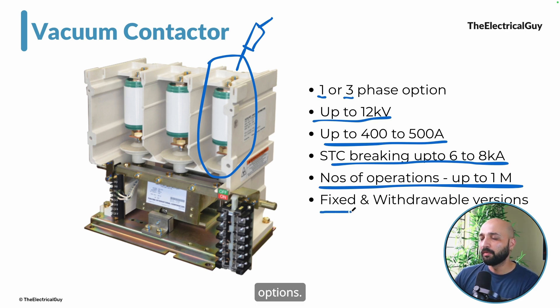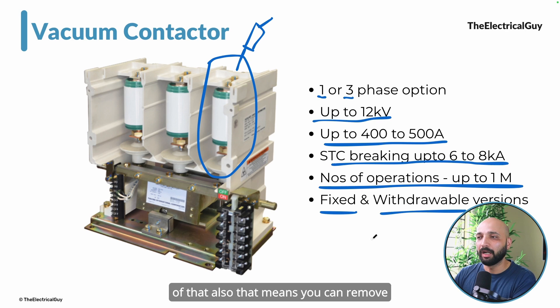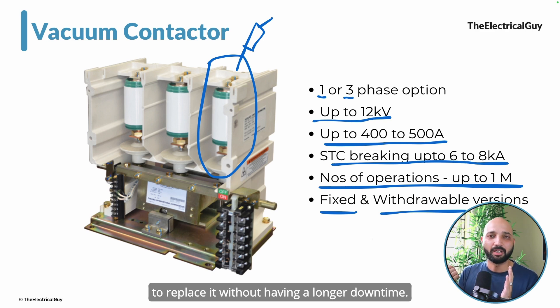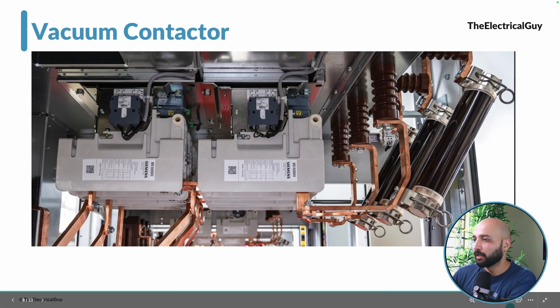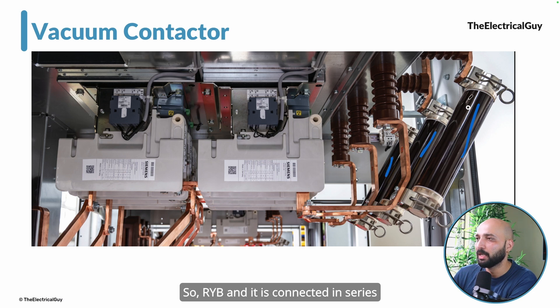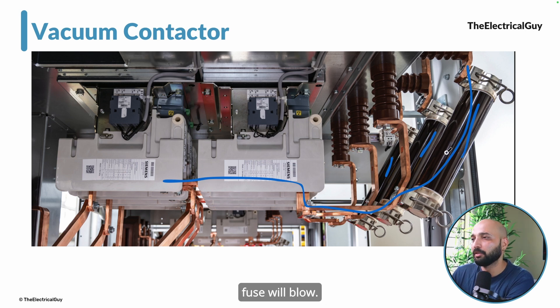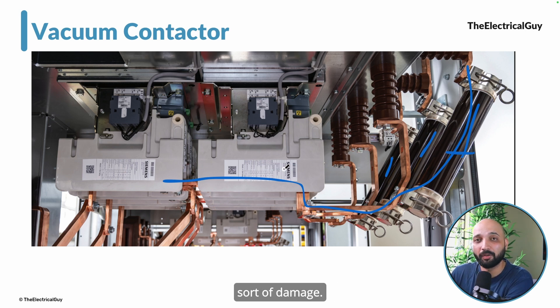Vacuum contactors are available in two variants: a fixed version installed permanently inside the panel, or a withdrawable version that can be removed from the panel for quick maintenance or replacement, minimizing downtime. A fuse can also be connected in series with the contactor — one fuse per phase — to provide short circuit protection. In the event of a short circuit, the fuse blows, and the contactor is protected from damage. You simply replace the fuse and reuse the contactor.